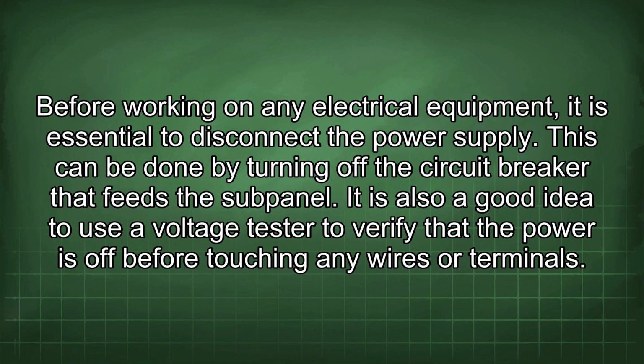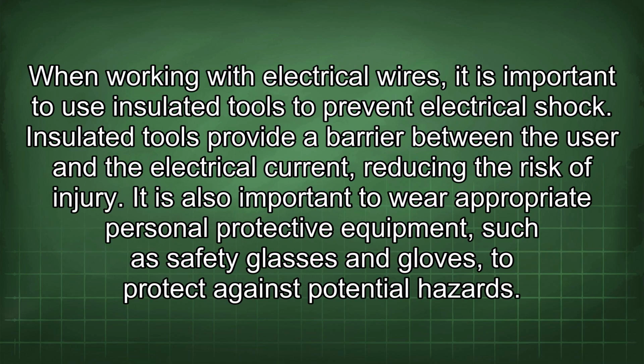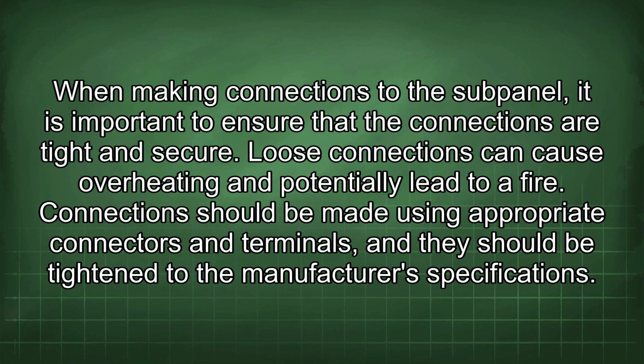It is also a good idea to use a voltage tester to verify that the power is off before touching any wires or terminals. When working with electrical wires, it is important to use insulated tools to prevent electrical shock. Insulated tools provide a barrier between the user and the electrical current, reducing the risk of injury. It is also important to wear appropriate personal protective equipment, such as safety glasses and gloves, to protect against potential hazards. When making connections to the subpanel, it is important to ensure that the connections are tight and secure. Loose connections can cause overheating and potentially lead to a fire. Connections should be made using appropriate connectors and terminals, and they should be tightened to the manufacturer's specifications.